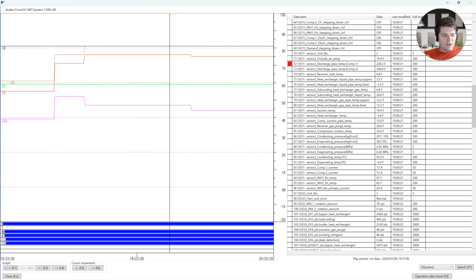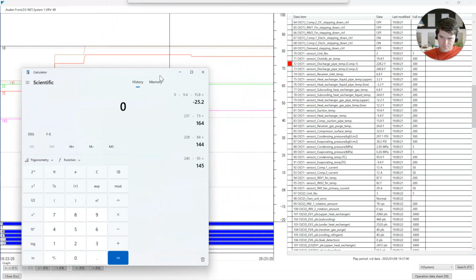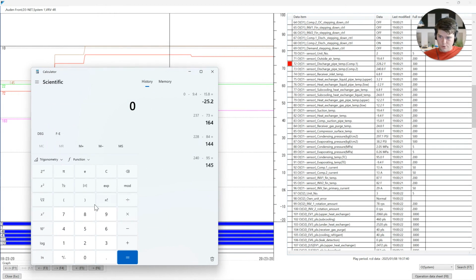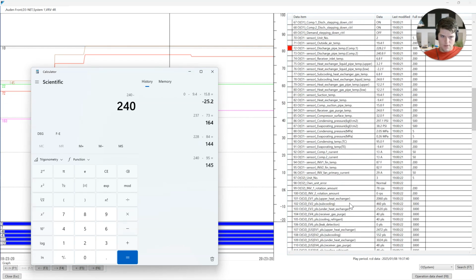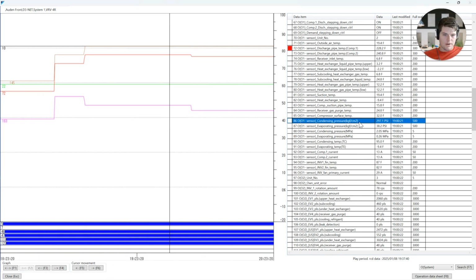Let's check our discharge superheat now. All right, so we're going to come in here and get our numbers pulled up. We're going to take our 240. I love taking the larger number here. 240 degree discharge pipe temp, compressor number 2, and we are going to subtract it from, oh, I don't have it populated on here, but it's right here.